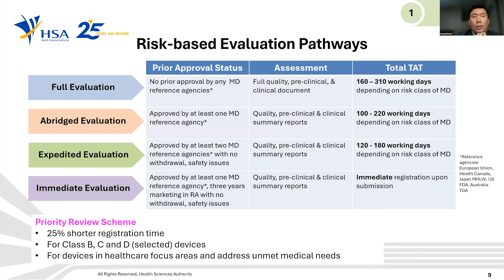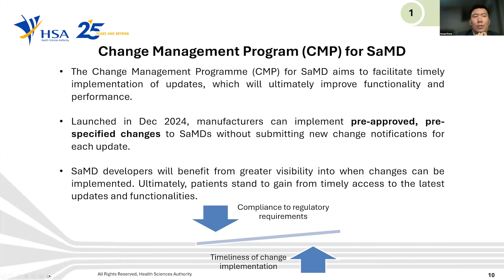One of the unique challenges of regulating AI as a medical device is that the AI systems change. They are updated, retrained, and also improve on a continual basis. To address this, we launched the Change Management Program for Software as a Medical Device in December 2024. The program allows manufacturers to implement pre-approved, pre-specified changes to their software as a medical device without submitting new regulatory application to us for each individual update.